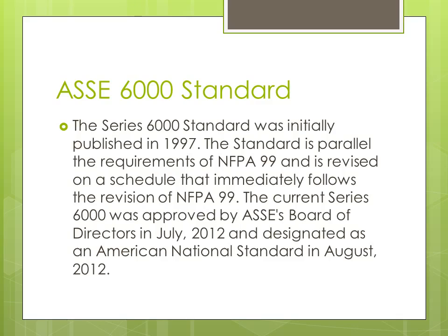A lot of folks are trying to get their heads around what this means. Well, primarily for the healthcare facility leader, what it means is for the installation, for any repairs, for any time you go into the system and you disrupt the system, you actively cut into the system, you fall under the ASSE 6000 standard. This is for the inspectors, the installers, the repairers who go, I would say, past the outlet. And this is where the confusion seems to be out there in our industry right now.